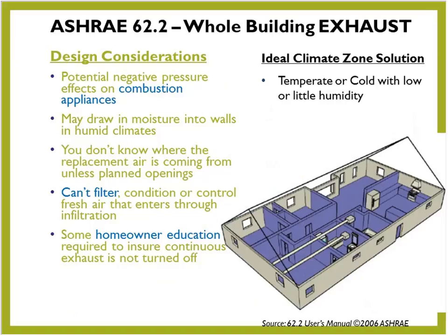And of course, on the end of those ducts, we want to have a termination with a lot of free open area, where it's not restricting the flow of air either, because you can put in a really nice fan, do a great job on the ductwork, but if the termination at the end is choking that fan, you're right back to where you started with all the elbows and stuff.